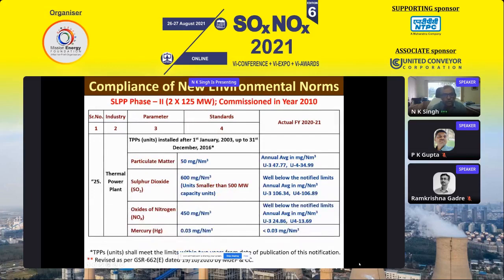Similarly, for phase 2, these units were commissioned in the year 2010, and the norms are different from the phase 1 units. But for particulate matter, if you see, it is 50 mg/NmÂ³, and our units' emission is 47.7 for one unit and 34.99 for another. So we are fully complying for this also. For this purpose, in both phase 1 and phase 2, we have done a lot of retrofitting work and revival of dummy fields. So that has helped us in meeting this on ESP. For SOx and NOx, we are fully complying with the technological advantage of CFBC.